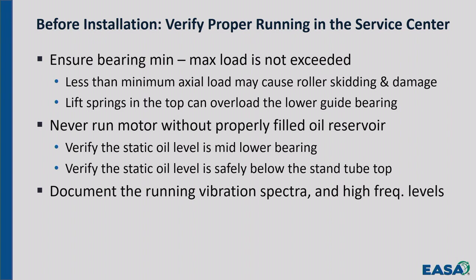And it goes out on the job site, and all of a sudden you have high vibration. You say, well, what was it when you test ran it? Well, we didn't check it. That's not going to cut it. You say, here's the spectrum. This is what it ran. We measured this. It ran fine in the service center.